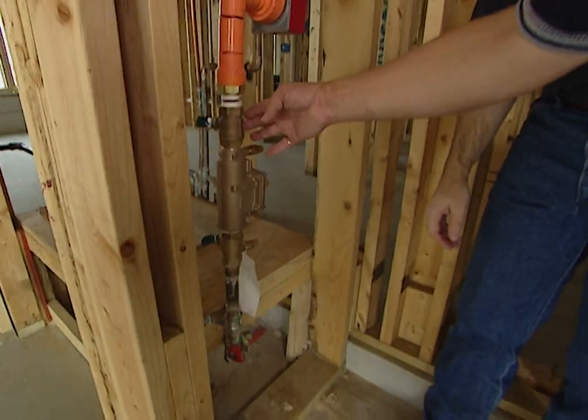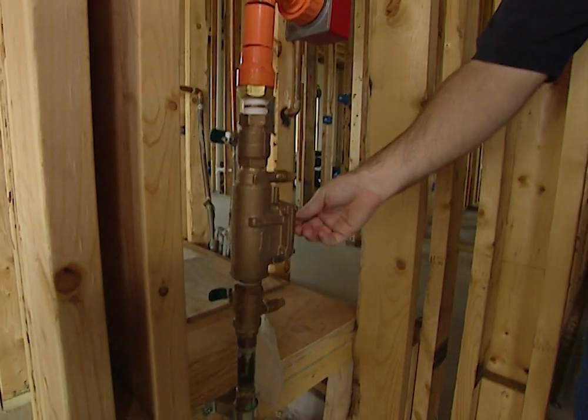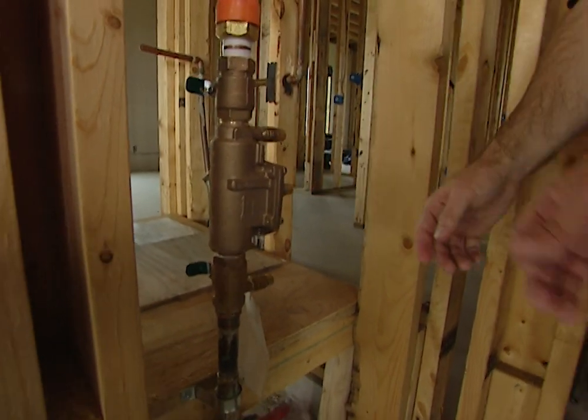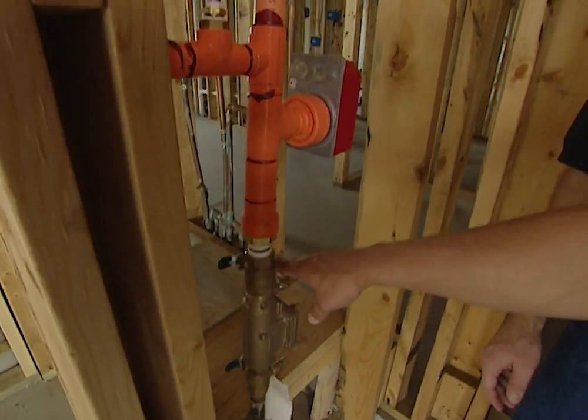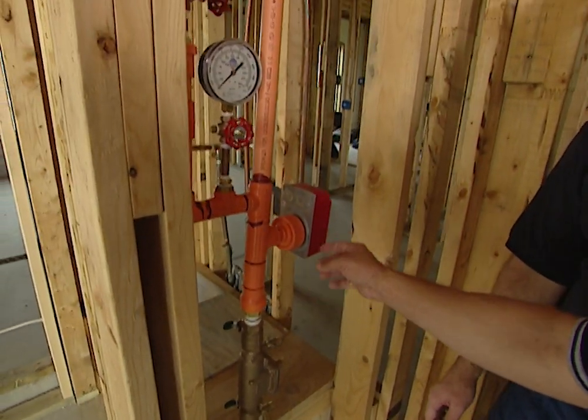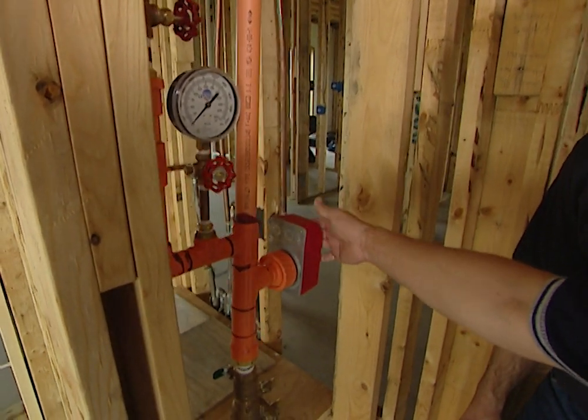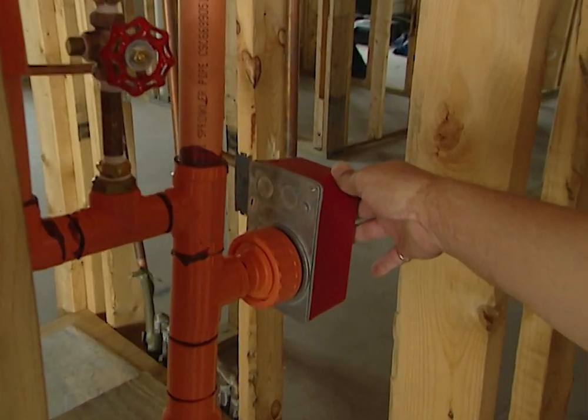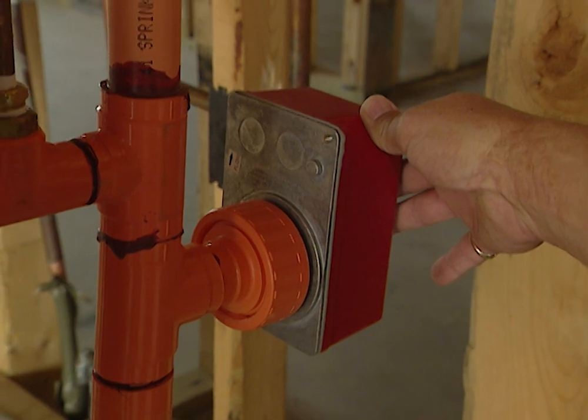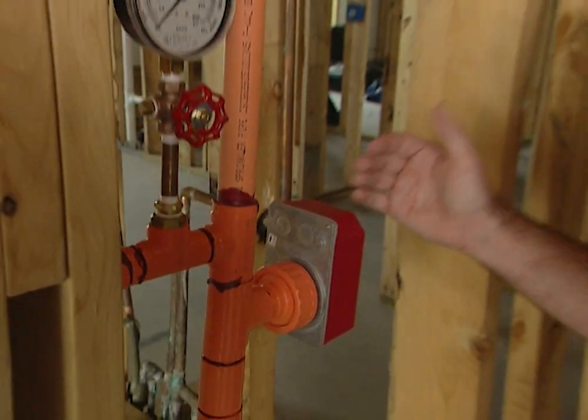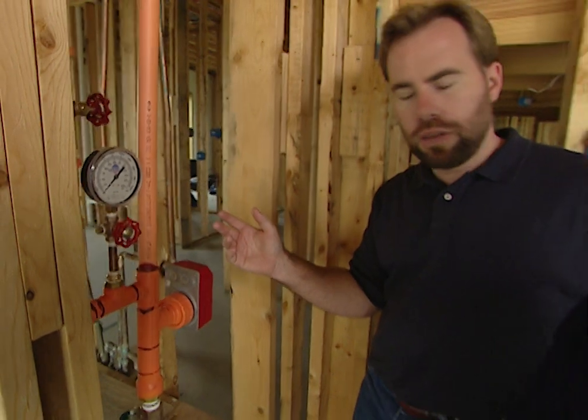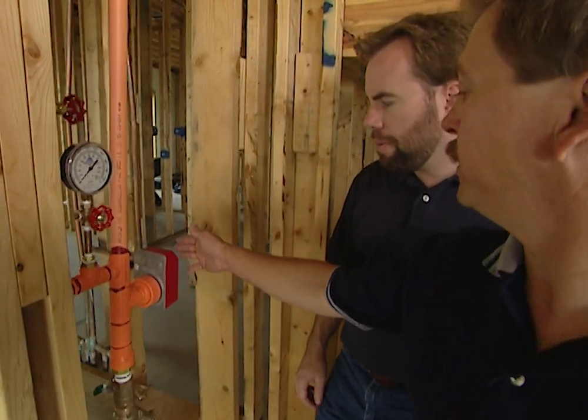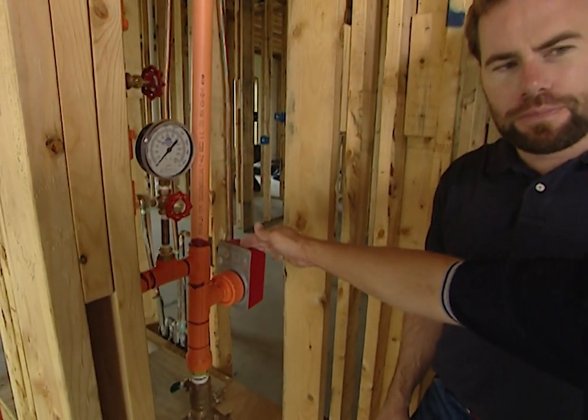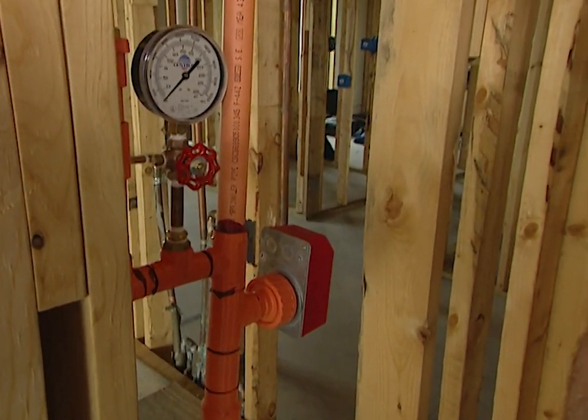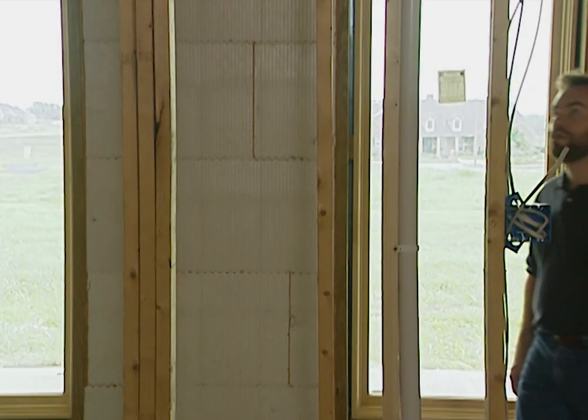Your riser assembly here, you have a backflow prevention device that's required now by most water purveyors or water authorities these days. We convert after the backflow device to a plastic. Then we have what's called a water flow detector. This is what sends your local audible alarm to your signaling device like a bell or a horn strobe. Okay, so besides the smoke detector, we will have an alarm when the sprinkler system goes on? Yes, sir. This can not only be local, it could also be monitored by a central station. So if you're not home, they know.